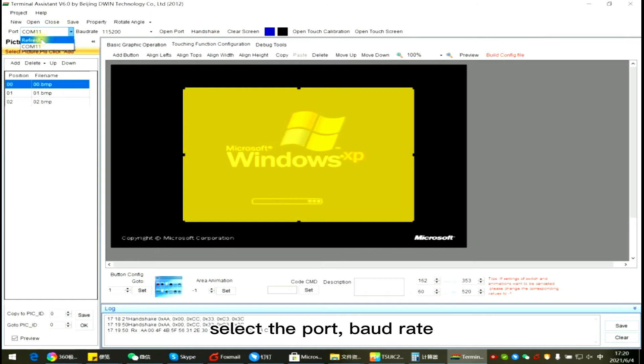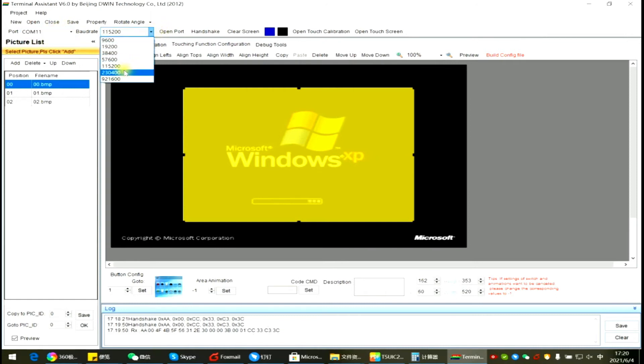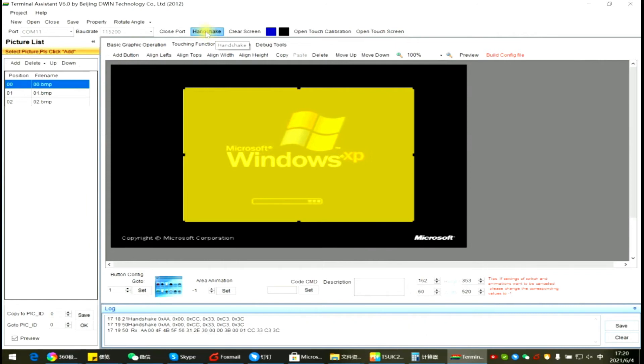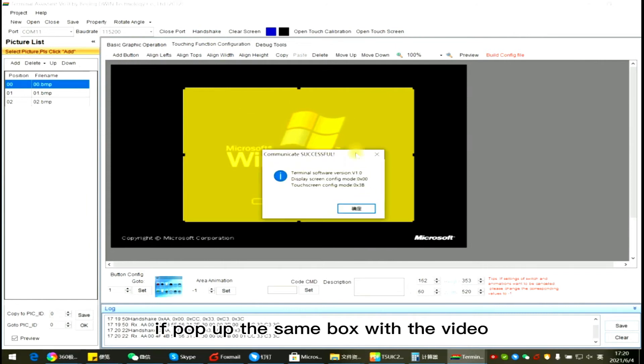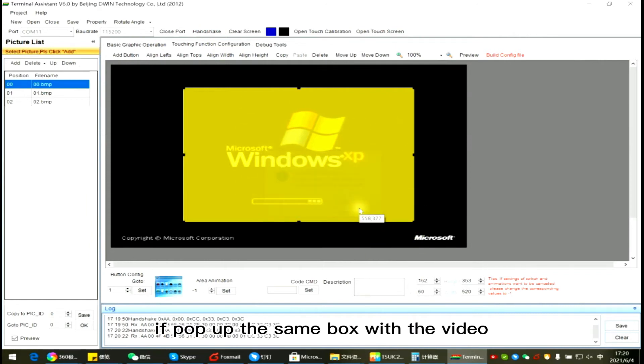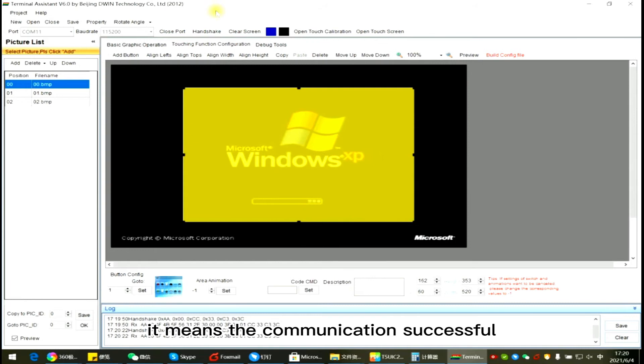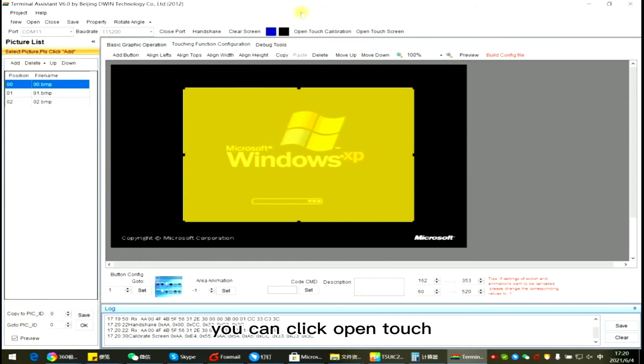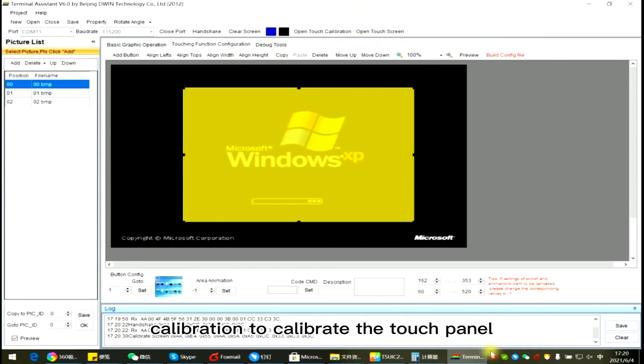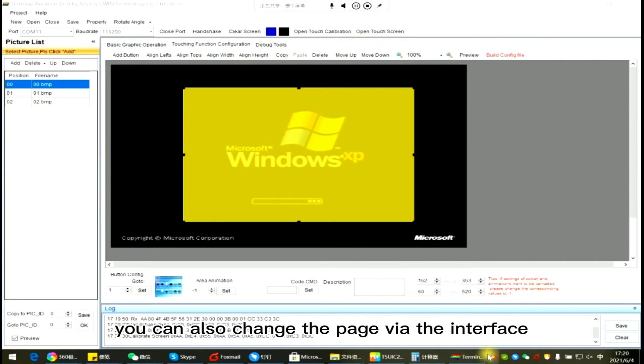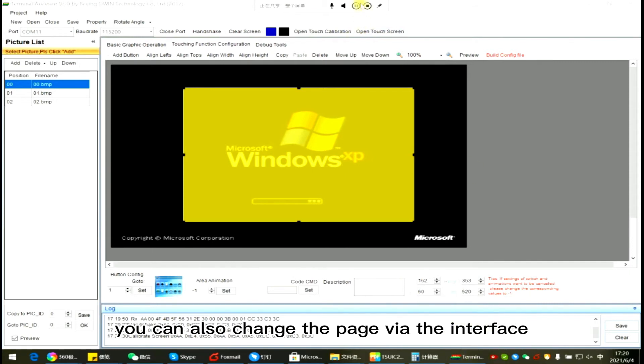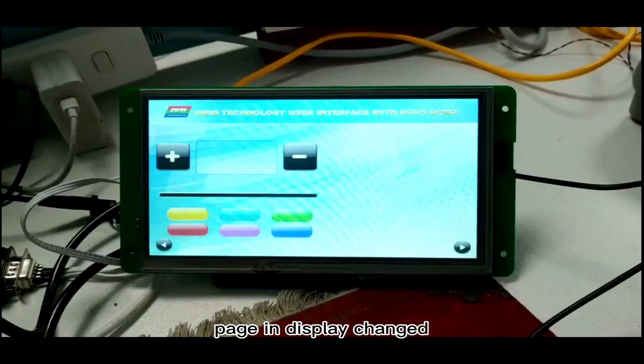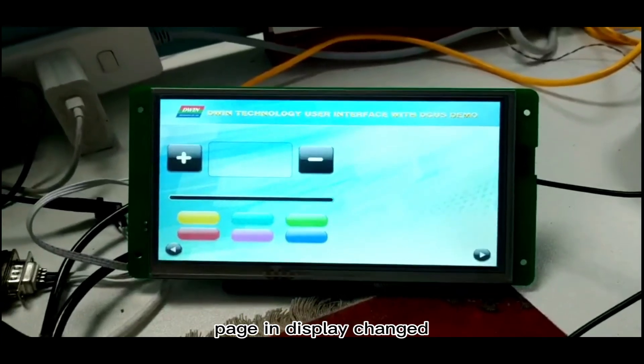Select the port. Click Open Port. Click Handshake. If pop up the same box with the video, it means the communication is successful. You can click Open Touch Calibration to calibrate the touch panel. You can also change the page via the interface. Select Go to Picture ID. Click OK. Page in display changed.